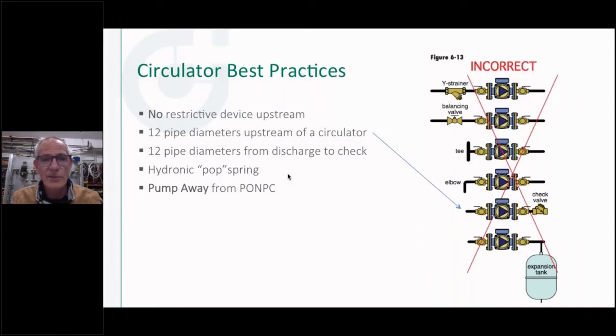So a couple slides here just answer some of the questions that were typed in as we were going last week, and it had to do with pumps and piping on pumps specifically, what to do and what not to do. The question I think was how many inches or feet of straight pipe upstream of the pump. And so there's our suggestion, 12 pipe diameters upstream. So if it's 1 inch pipe, a foot; 2 inch, 24 inches. And that just makes sure that the flow kind of straightens out before it gets into the inlet side of the circulator.